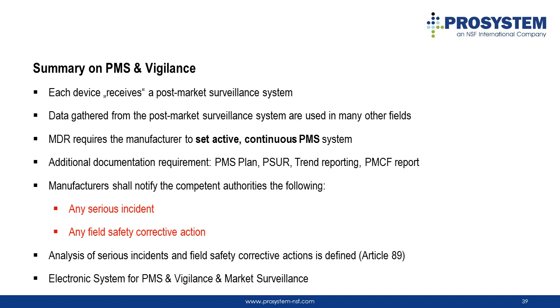For the vigilance part, manufacturers should notify the competent authorities if any serious incidents happened or any FSCAs were taken. In addition, how to analyze the serious incidents and FSCAs is defined. Last but not least, the transparency will be further increased by the electronic system for PMS and vigilance and market surveillance.